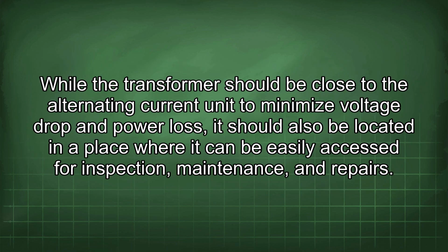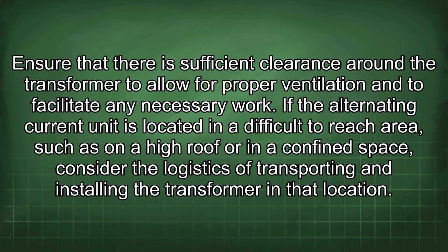While the transformer should be close to the alternating current unit to minimize voltage drop and power loss, it should also be located in a place where it can be easily accessed for inspection, maintenance, and repairs. Ensure that there is sufficient clearance around the transformer to allow for proper ventilation and to facilitate any necessary work.